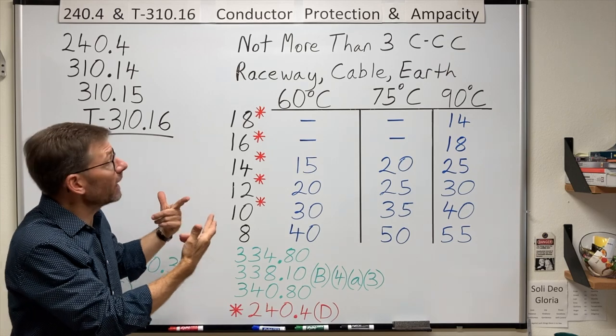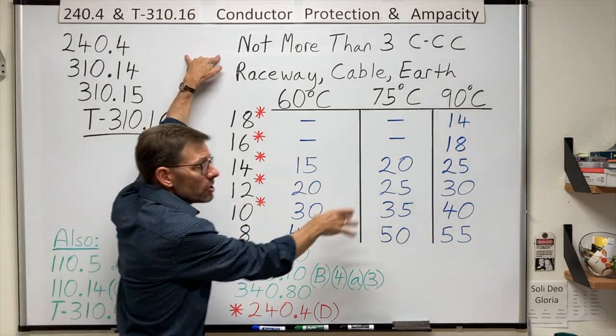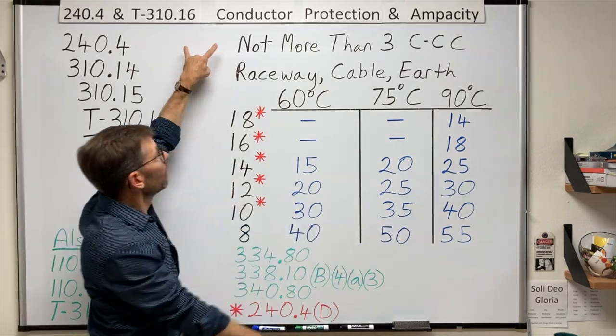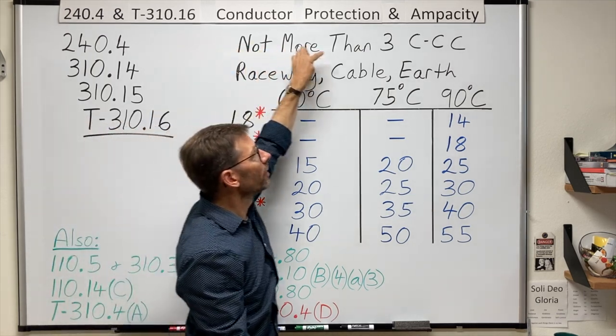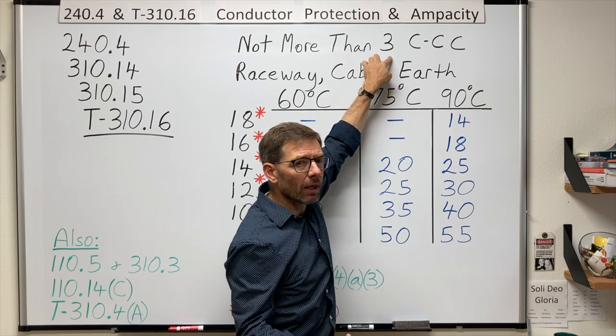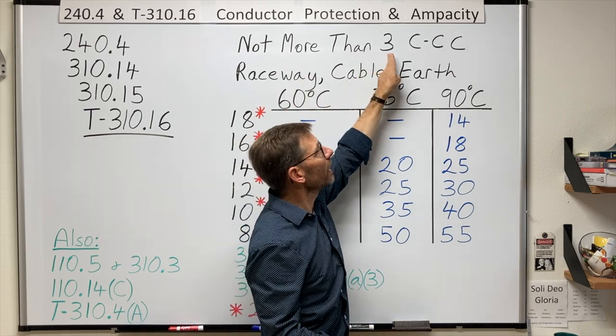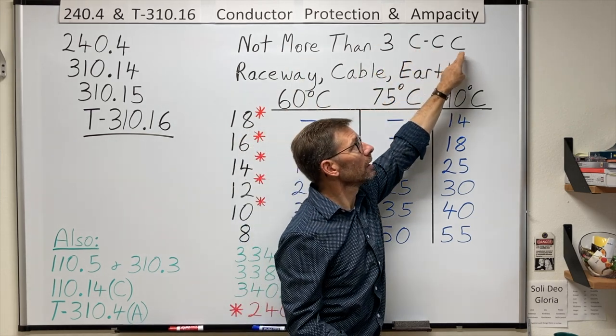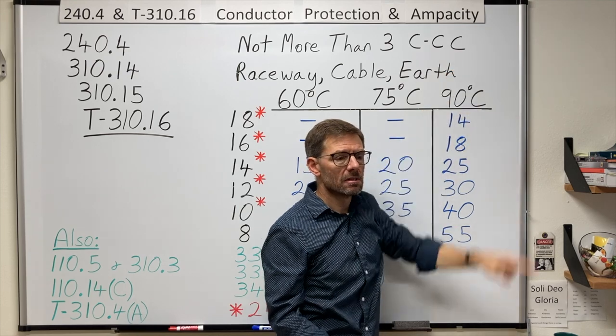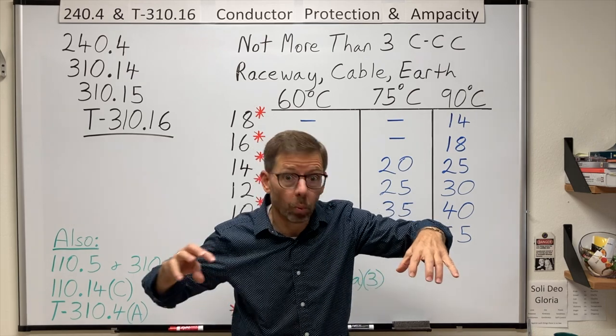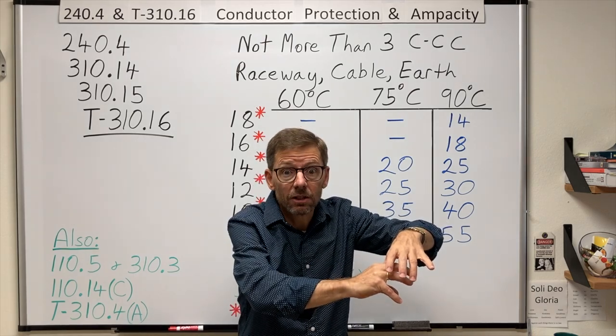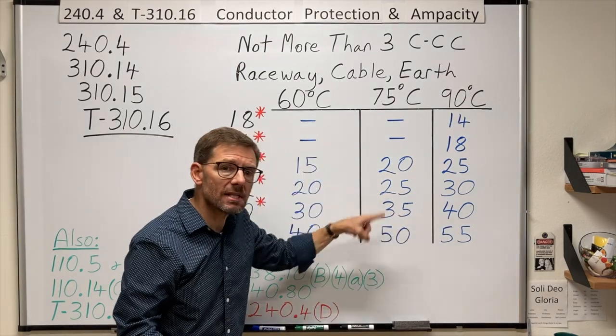Another thing I want to see in the title is that it says, use these ampacities for insulated conductors with not more than three, three what? Not more than three current carrying conductors. So, right away you go, Dave, many times I've had a conduit with way more than three conductors in it. Can I use these ampacities?